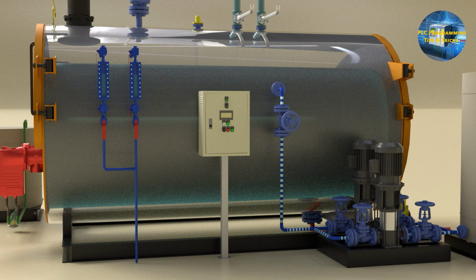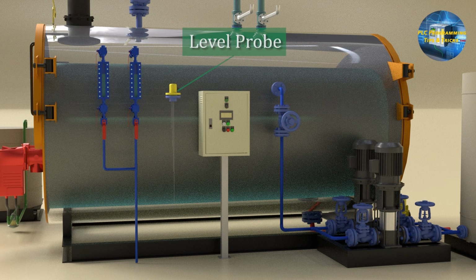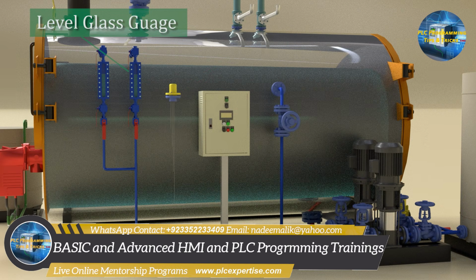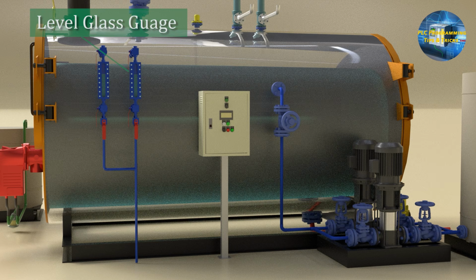A water level probe is installed in the boiler shell. It detects low level, high level, very low level, and very high level. This probe starts the pump at low level, stops the pump at high level, and triggers alarms and shuts down the boiler at very low or very high water levels. Two visual water gauges are also available for the operator to monitor the water level inside the boiler.